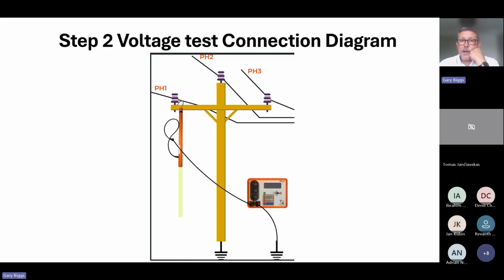So for the purposes of today, if the steelwork was more than 300 volts but less than 2.7 kV, we know that we have an insulator that is breaking down, but it's not completely broken down, as it were. So the system would remain live.